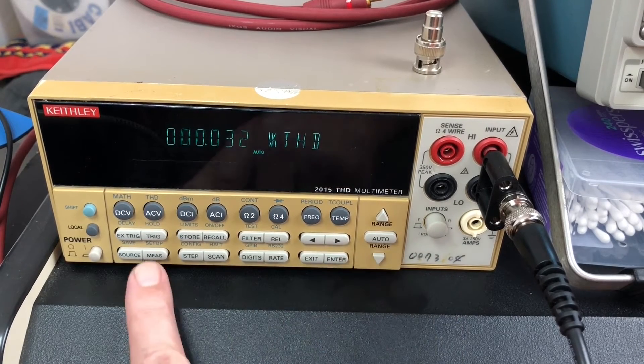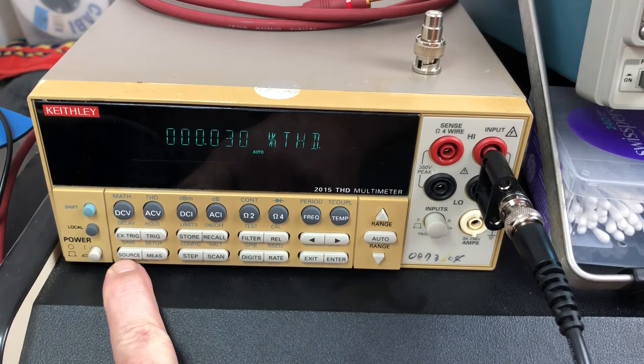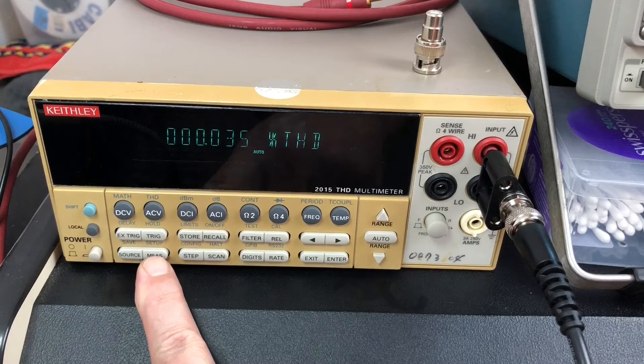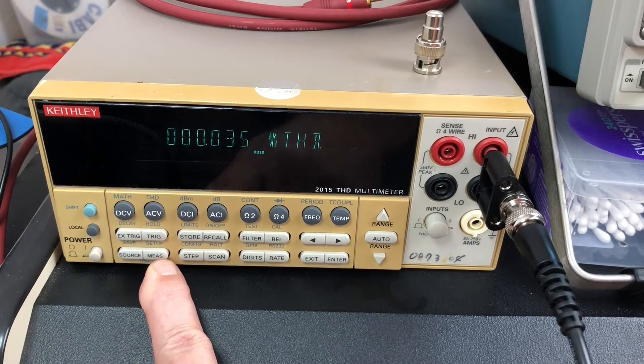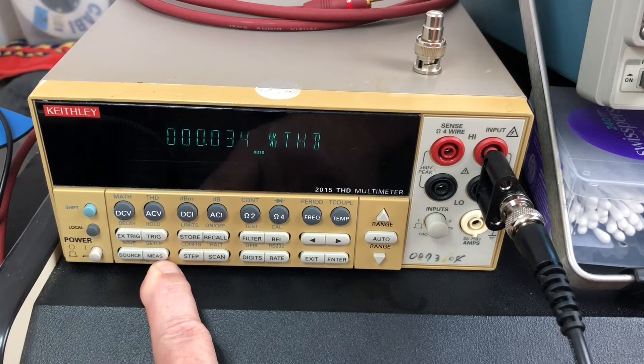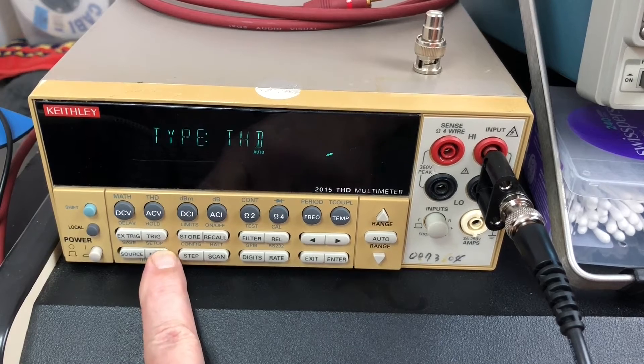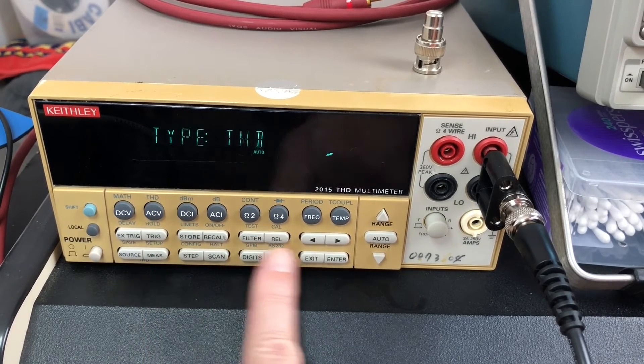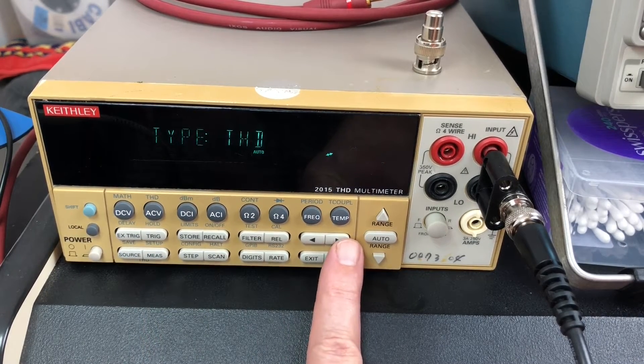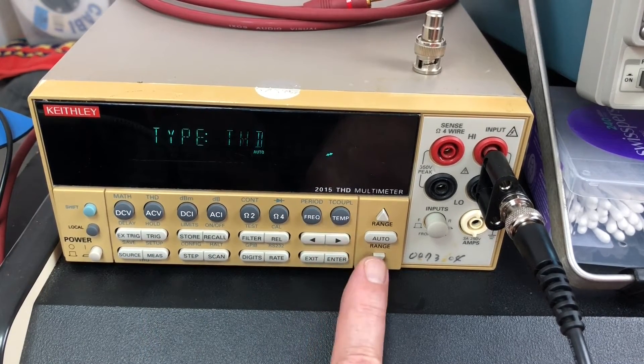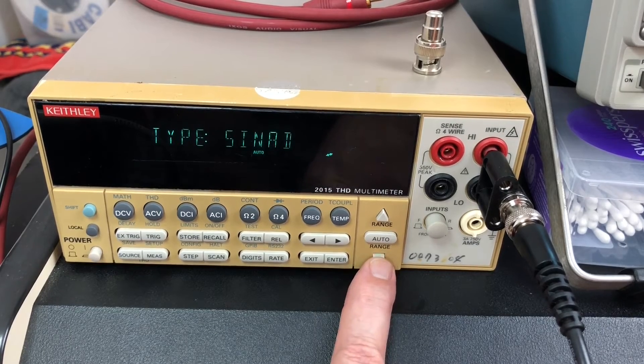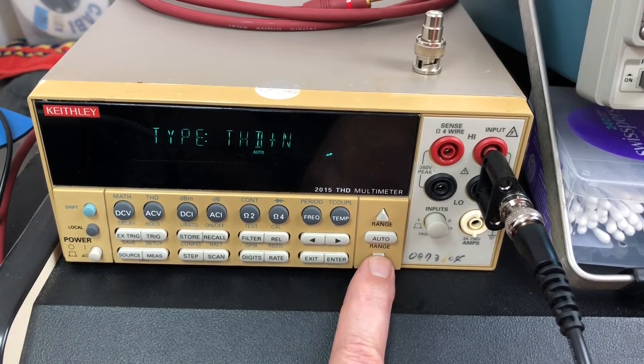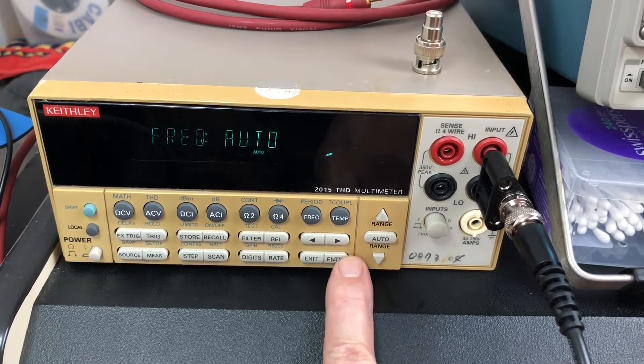This button here is the configuration for the actual THD measurement. This device does three types of measurements: THD, SINAD, or THD plus noise. I'm just doing THD.